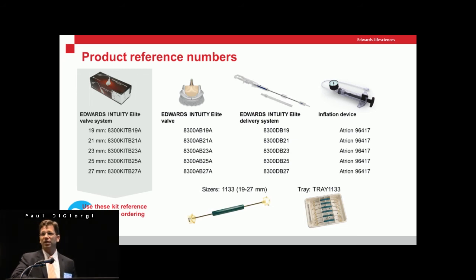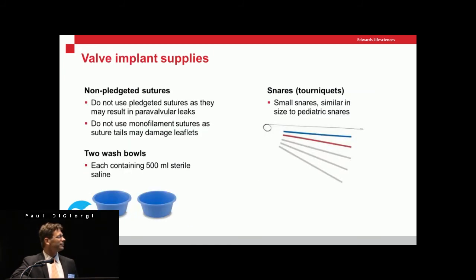I wish they made them every millimeter rather than every two millimeters, because it really has to be an exact fit. With a sutured valve that precision is not required. They don't make sizes beyond 27, and then for 29s there's nothing available — that's a nuance we're still learning. The sizing is probably the most important part of this valve. That said, everyone can deliver this valve and balloon it in — it's not idiot-proof, but it's pretty good, especially for surgeons not used to doing balloon work.